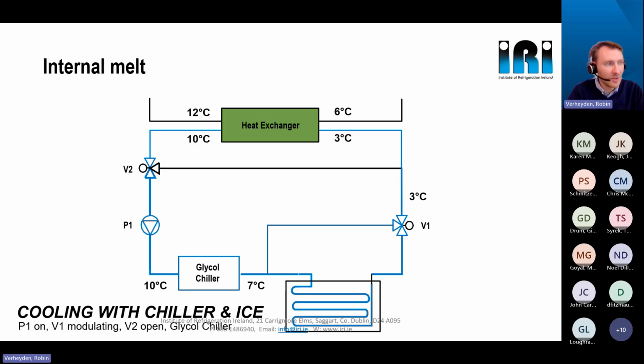What will happen now is that the V2 three-way valve will be activated to pass the flow through the heat exchanger, and via the valve V1 on the right side, we will modulate this valve to be sure that the combination of the water coming directly from the chiller and the water passing via the ice thermal storage tank gives a nice mixture temperature of, in this case, 3 degrees.